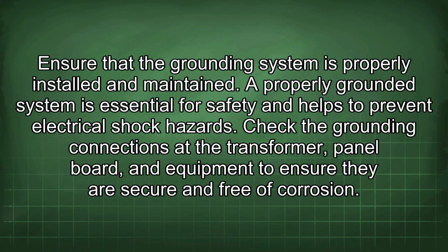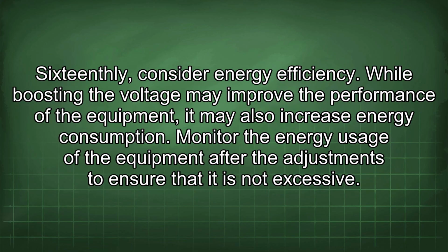Check the grounding connections at the transformer, panel board, and equipment to ensure they are secure and free of corrosion. 16thly, consider energy efficiency. While boosting the voltage may improve the performance of the equipment, it may also increase energy consumption. Monitor the energy usage of the equipment after the adjustments to ensure that it is not excessive.